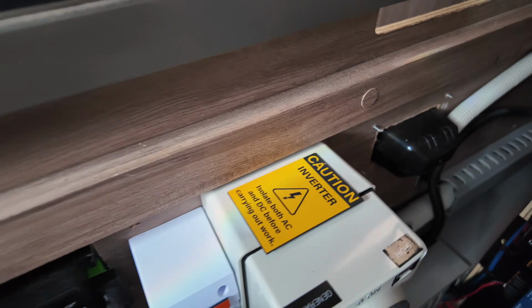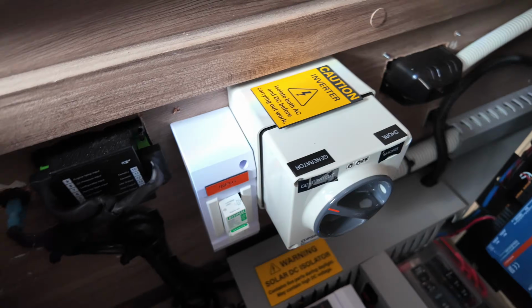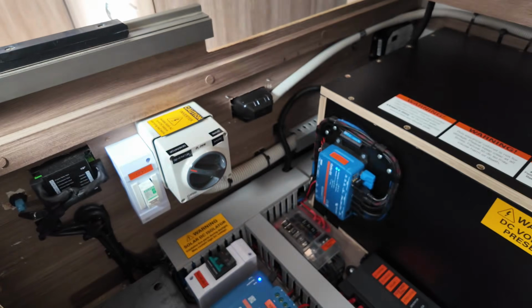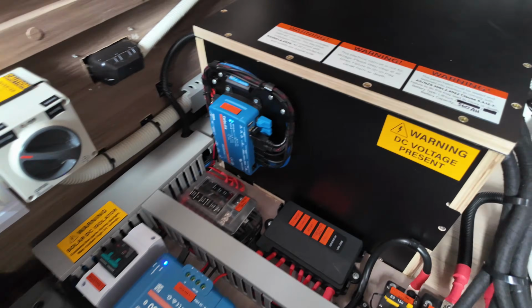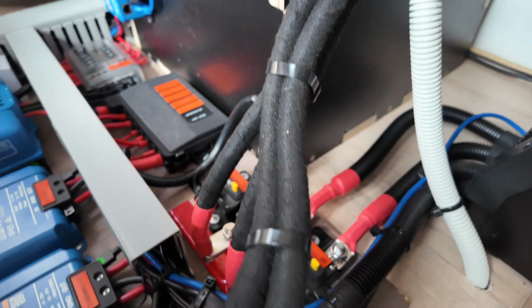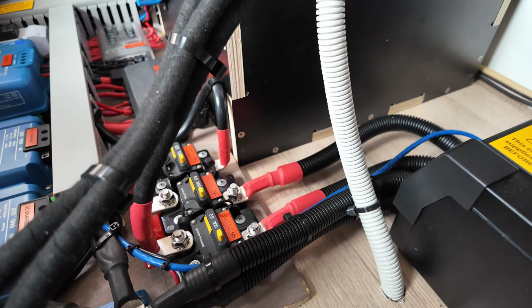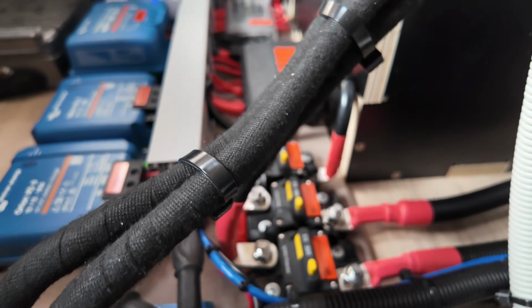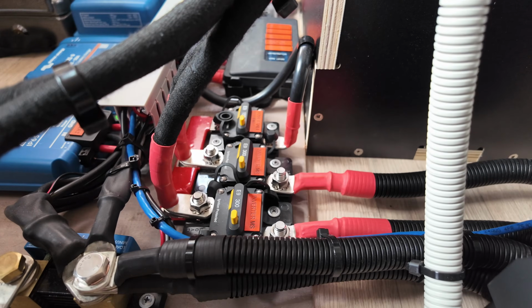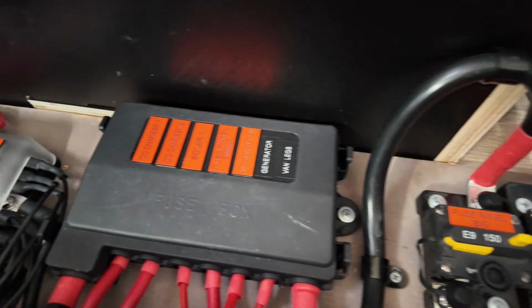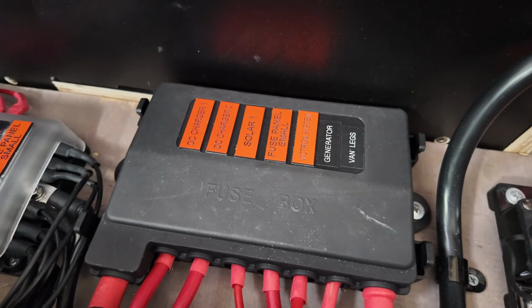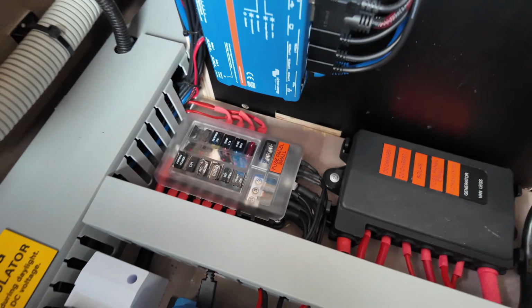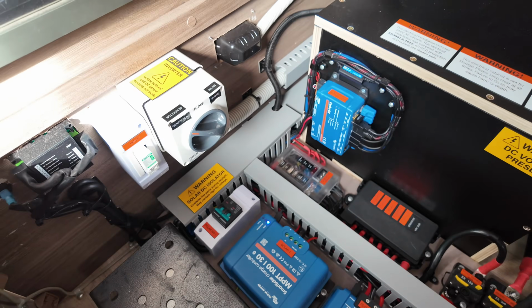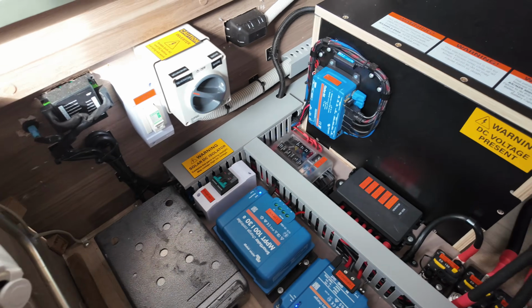We've got a transfer switch to select from generator or shore power, the Cerbo to talk to the screen, and the solar main switch. We've run 2 70mm cables to the 5 kVA, both running through 300 amp manual reset circuit breakers. Another circuit breaker looks after this fuse panel, and then these MIDI fuses look after the bigger loads, then we go into some of the original stuff plus some stuff we've added on the smaller fuse panel.